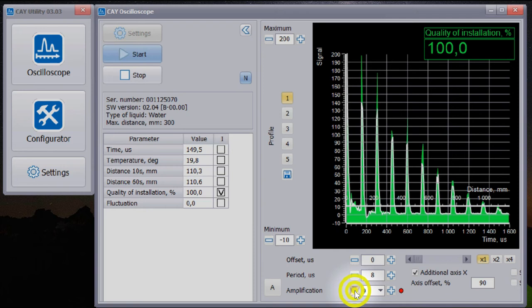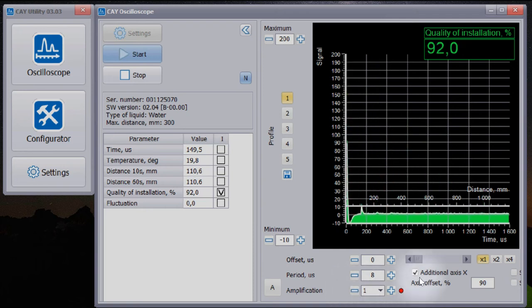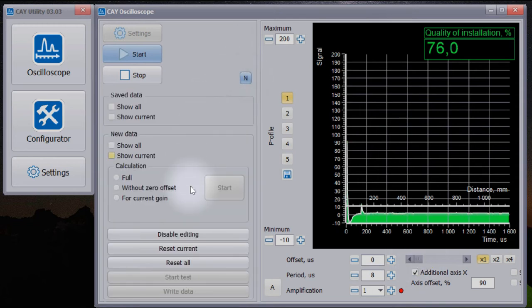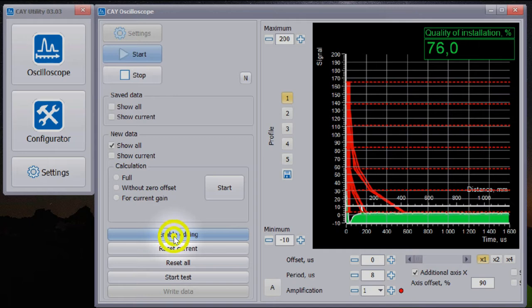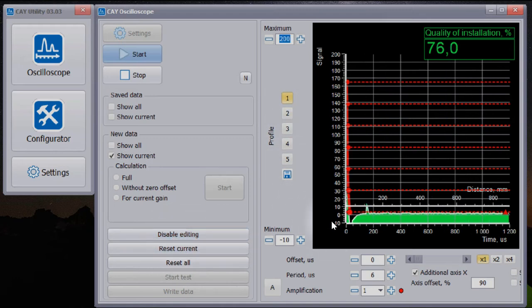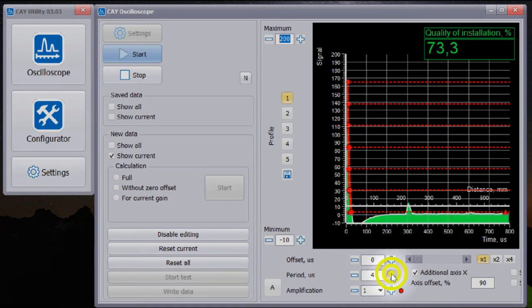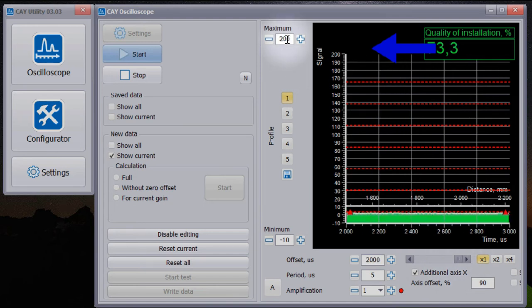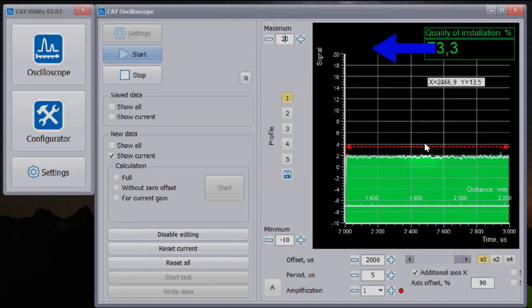Then we will set up the sensor's noise protection. Set the minimum amplification value to 1. Click N to enter the Noise Reduction Editor and switch on Edit mode. Noise consists of a constant part caused by sensor components and a variable part which is caused by installation and tank properties. We will try to remove the constant noise part at first. Horizontal line with triangle: sensitivity limit. Increase resolution to maximum. Noise should not intersect our sensitivity limit line. This line must be above noise.